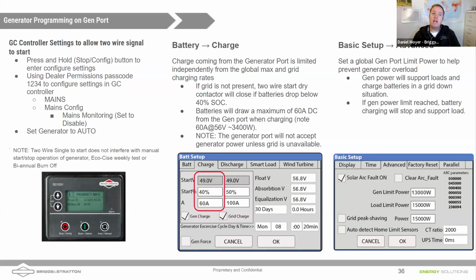You need to go in there and change the configuration so that mains monitoring, if it does still see the presence of grid, it still will start up if it sees the two-wire signal to start. Yep. So we'll disable that. We're going to disable mains monitoring, and we're going to set it up for two-wire signal to start by doing that. In the interest of time, I'm going to run pretty quickly.